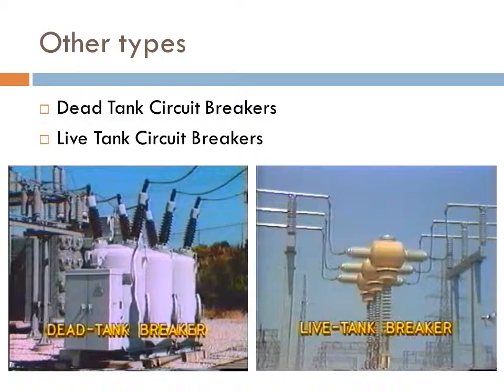Circuit breakers can also be classified based on grounding. There may be dead tank circuit breakers, live tank circuit breakers. The dead tank circuit breaker is solidly grounded, while the live tank circuit breaker is grounded through an insulator.